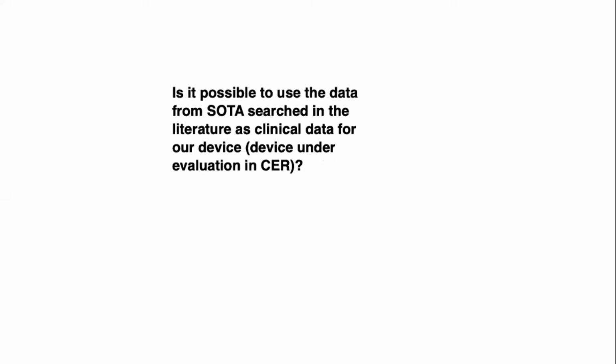I'm going to go out on a limb and say the short answer to that question is no, because the state-of-the-art specifically is looking at competitor data. It's looking for the state-of-the-art landscape, the therapeutic landscape, the competitor device or devices data. That's why you can use pooled data, meta-analyses, systematic reviews, even ones in which your own device may be a part of those systematic reviews or pooled data. But the point is that it's not data purely on your own device under evaluation.